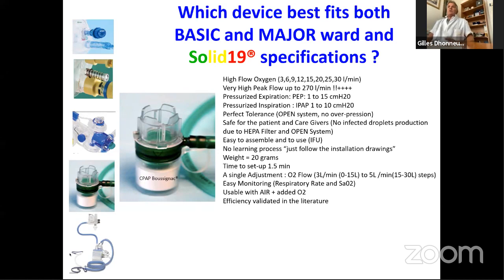So we analyzed all the devices we had. All of them were fitting the basic specification, but only one complied with the major ward use specification. It is called the CPAP of Boussignac. It's a very high flow oxygen system. It uses 3, 6, 9, 12, 15, 20, 25, 30 liters per minute. It has a very high peak flow. I think it's the highest peak flow on the market, even compared to an ICU ventilator. We measured 270 liters per minute peak flow for this machine, maintaining a stable inspiratory pressure within the mask.